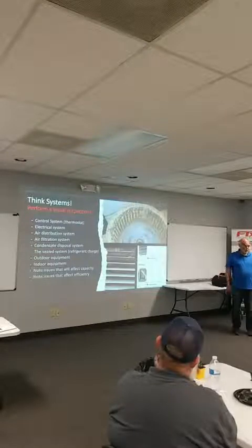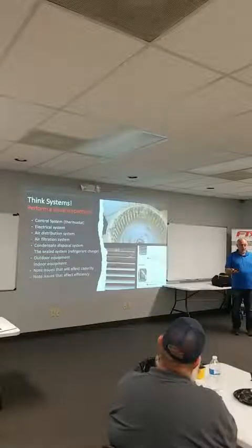In the system, right? Every time we're hooking gauges up to the system, and guess what? It doesn't even take refrigerant flow to get that moisture in there. If you have moisture in your hoses, it's gonna go right by vapor pressure, just like a sponge. It's gonna go straight out of your hose into that system. Right now, luckily we have a dryer on there, but that dryer does not have an infinite capacity. Eventually it gets to the point where moisture goes in, moisture goes out.